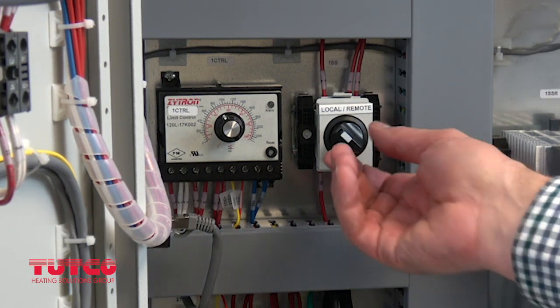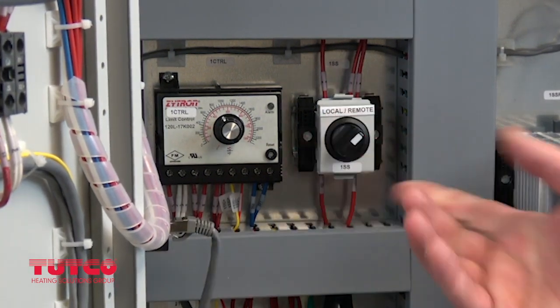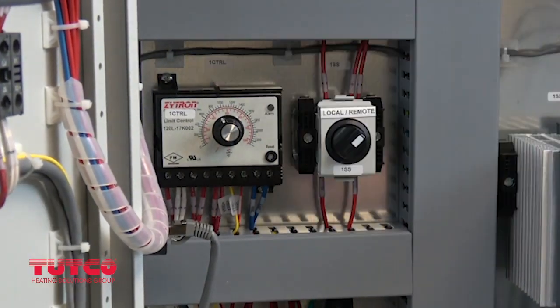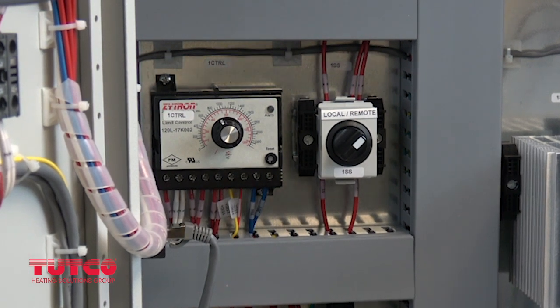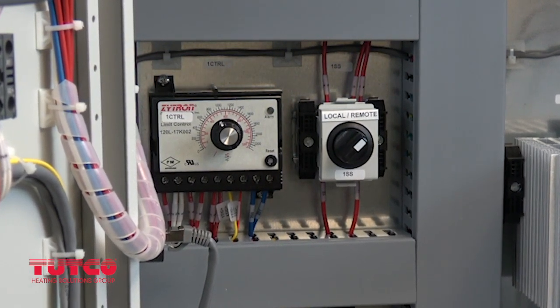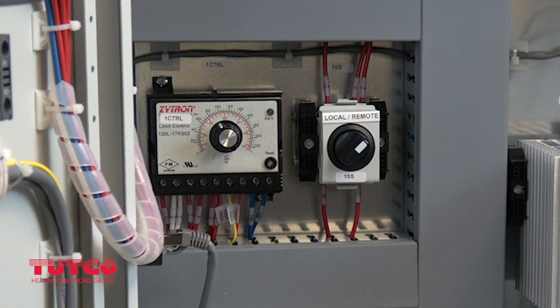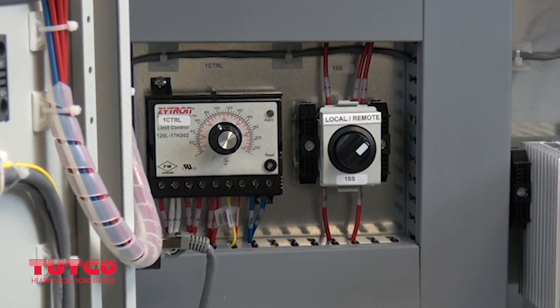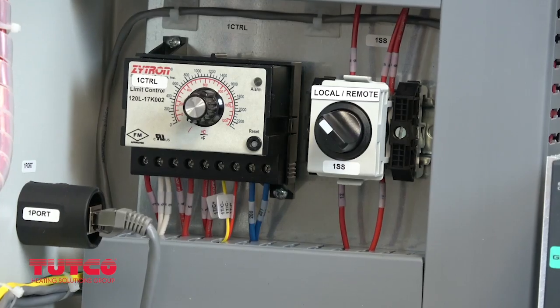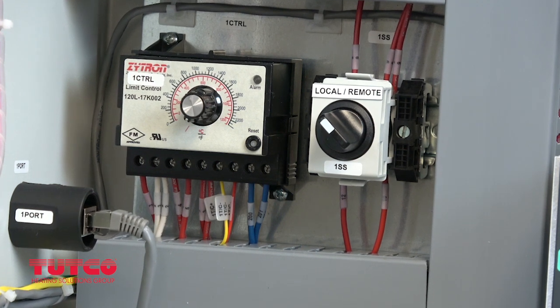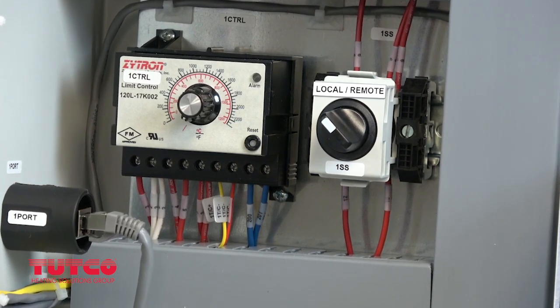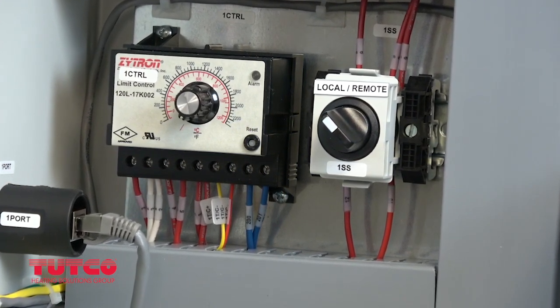When you switch to remote, the controls on the front of the panel, including start, stop, reset, will not function. The LEDs will light up, however. All commands will now come from a remote station or PLC when in remote. Next to the local and remote selector switch is the temperature high limit setting. It's a manual temperature setting that limits power to the heater.